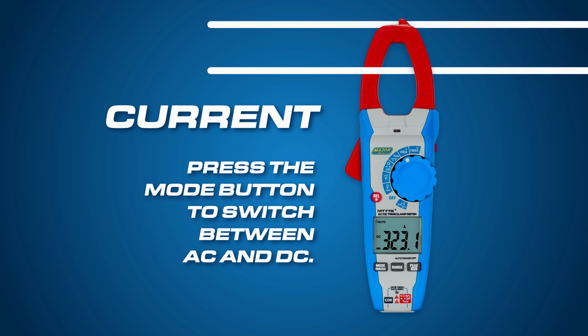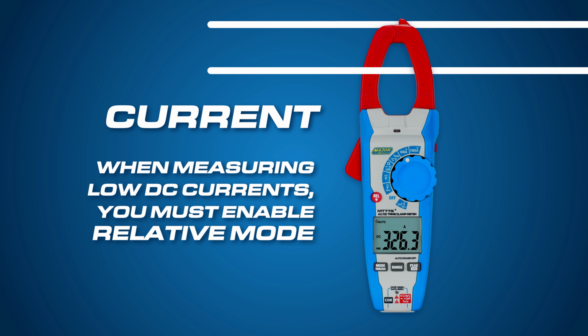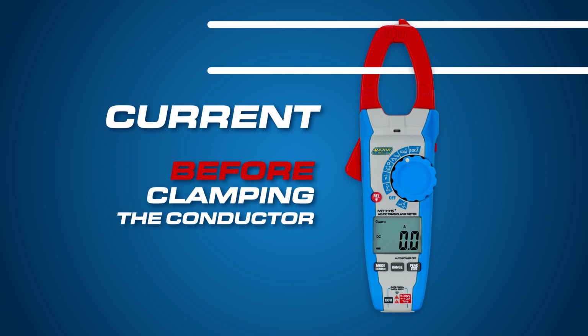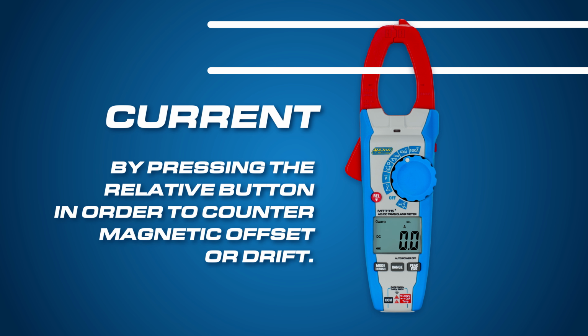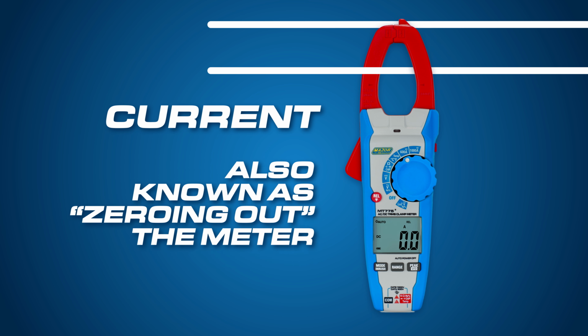Press the mode button to switch between AC and DC. When measuring low DC currents, you must enable relative mode before clamping the conductor by pressing the relative button in order to counter magnetic offset or drift, also known as zeroing out the meter.